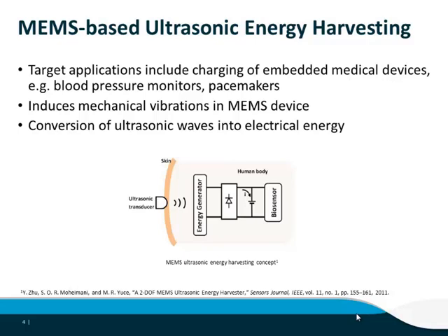An example application would see a MEMS harvester integrated into a device placed inside the human body, such as a pacemaker or blood pressure sensor, while an ultrasonic transmitter above the surface of the skin emits ultrasonic waves through the body towards the device, inducing a mechanical resonance in the system. This mechanical displacement can then be converted by the harvester into electrical energy to help power the system.